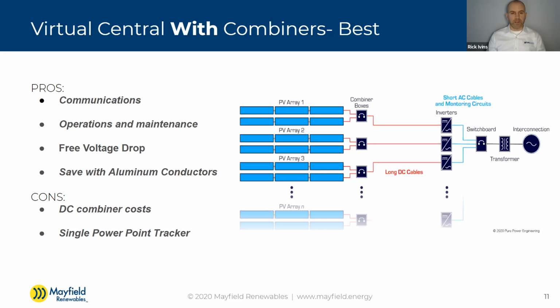Well, two different answers for the 1000 or 1500 volt. If you're at 1000, you've got combiner boxes available in that voltage that give you arc fault circuit detection and interruption. When it comes to 1500 volt, that becomes a challenge, not just in the combiner box, but in the inverters themselves as well. There are extremely limited products out there, if any at all. We struggle to find any. Last year, there was one manufacturer making a combiner box with 1500 volt AFCI, but they stopped providing them. So they probably ran into some technological issues. But it's just not really available, so you can rely on other areas of the code to get around that, such as 90.4.